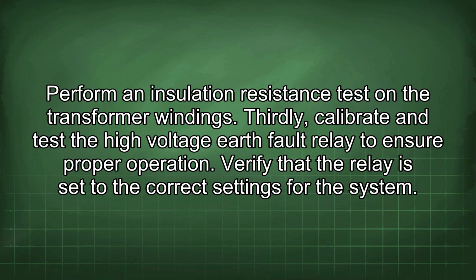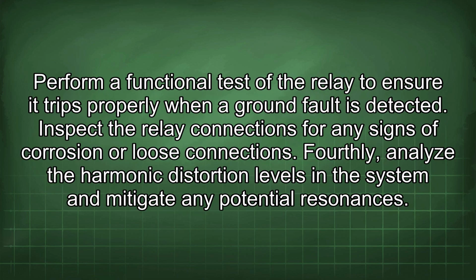Thirdly, calibrate and test the high voltage earth fault relay to ensure proper operation. Verify that the relay is set to the correct settings for the system. Perform a functional test of the relay to ensure it trips properly when a ground fault is detected. Inspect the relay connections for any signs of corrosion or loose connections.